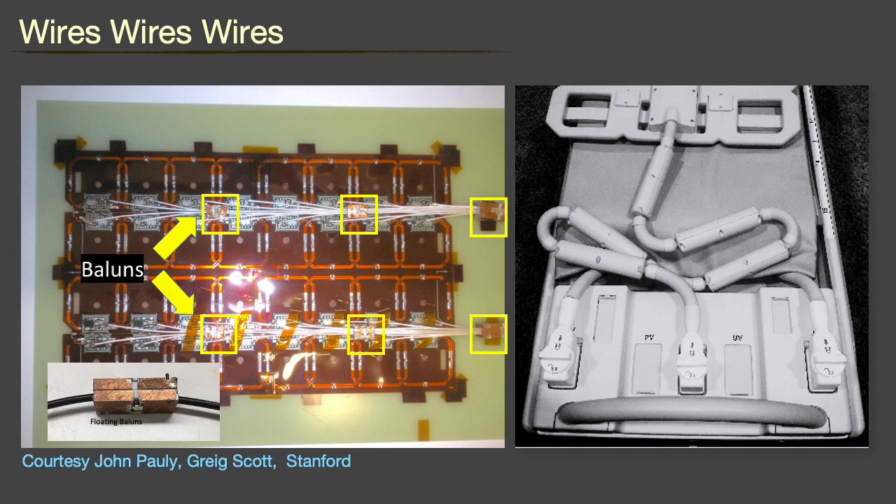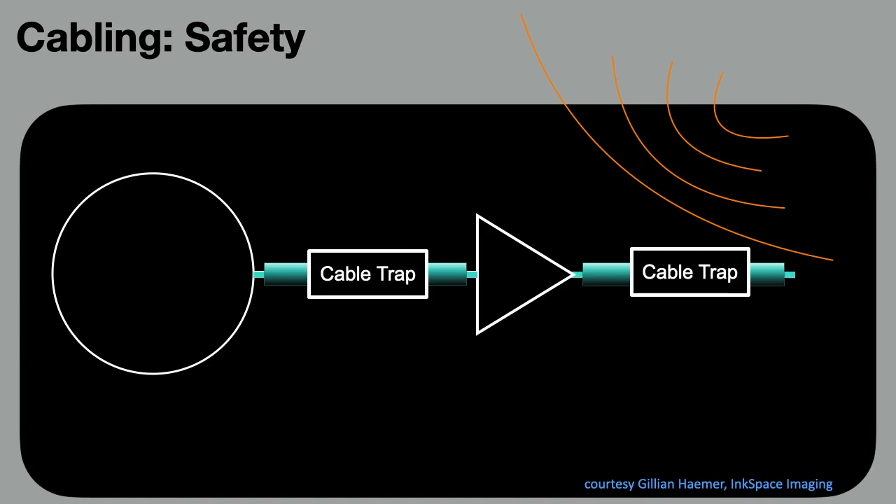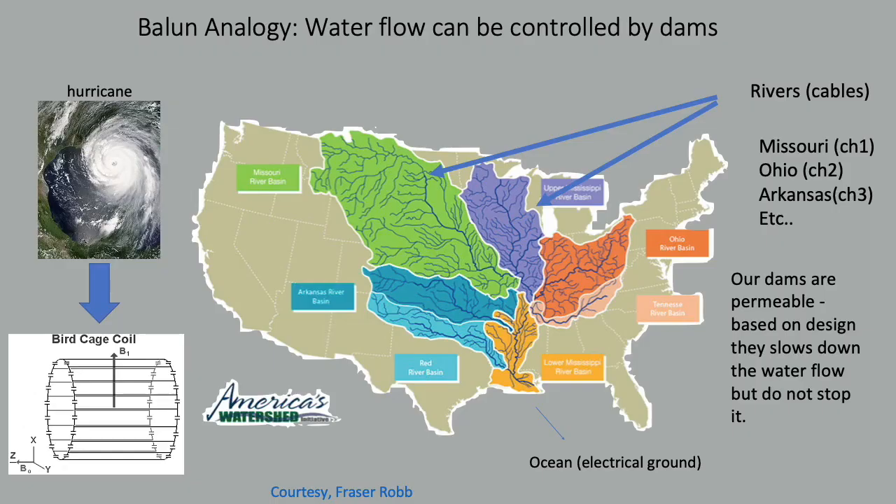The untold secret in the coil business is that most problems come from cabling. RF engineers spend most of their time routing cables and putting RF traps or baluns to minimize parasitic coupling to elements and the body transmitter, as well as manage heating. This issue becomes a real nightmare as channel count increases. The coil element is not the only conductor which interacts with the transmit field — during transmit, very high currents can run on the shield of a coaxial transmission line, endangering the patient. To reduce these currents, cable traps are placed along the conductors within the bore. This analogy, courtesy of Fraser Robb, likens the addition of cable traps to the damming of the Mississippi River, where different states are coil elements and the Gulf of Mexico is the system ground.